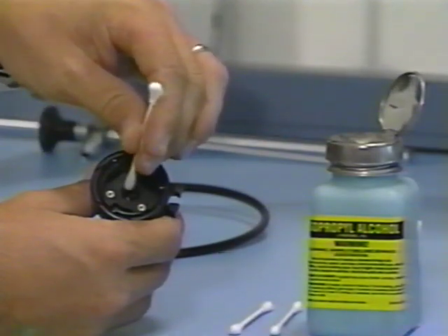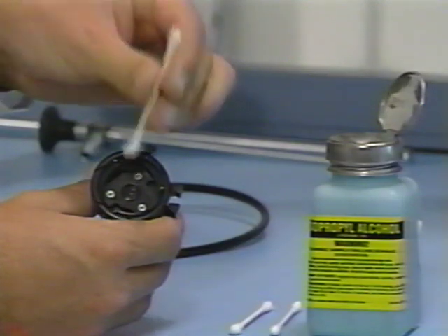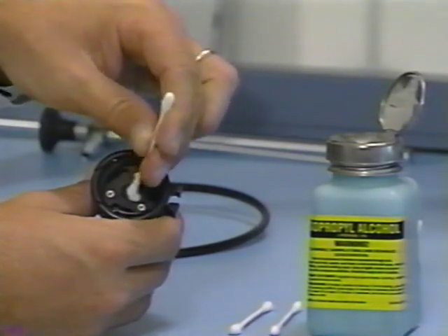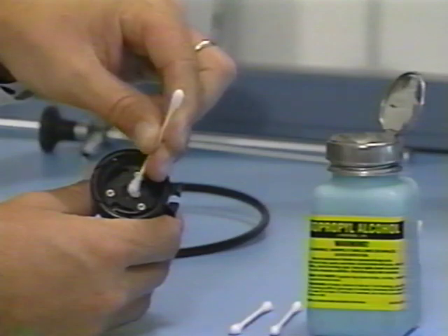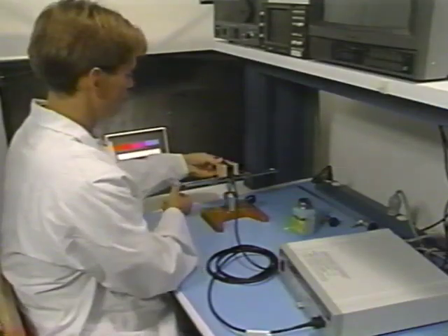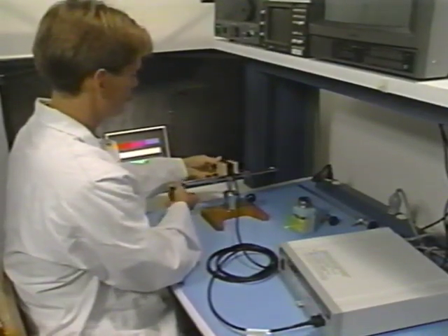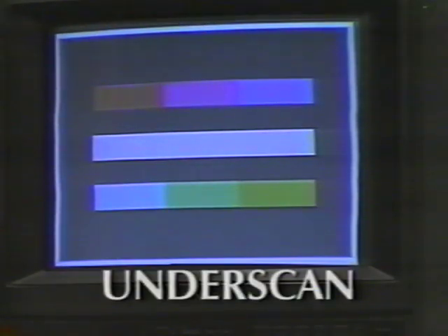Clean the optical window of the camera head with a cotton swab and alcohol solution to ensure that the lenses are clear of smudges and debris. Place the camera head in the vise and turn it on. Align the picture so that the color chart fills the entire screen of the monitor in the underscan mode. The white borders of the chart should be visible. The borders will not be visible in the normal scan mode.